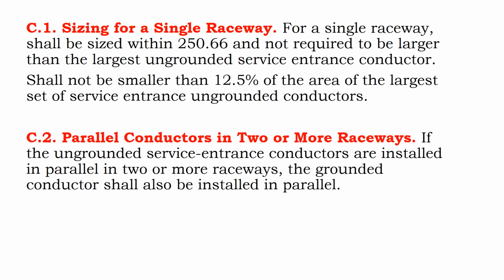Parallel conductors for two or more raceways. If the ungrounded service entrance conductors are installed in parallel in two or more raceways, the grounded conductors should also be installed in parallel. What's important about this is you might find in your designs that it might be easier to do two runs of 4/0 cable or 2/0 cable than to get up into your more industrial cable sizings. Like 250 kcmil is fine. I've even done wire runs of 750 kcmil, which is about as high as it gets, but it wasn't worth it just to have one cable in one conduit that's a very heavy, tough to bend cable. We should have just broken it into two smaller cables and done a parallel run.